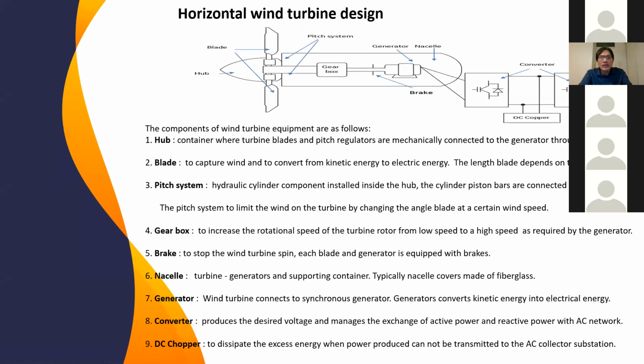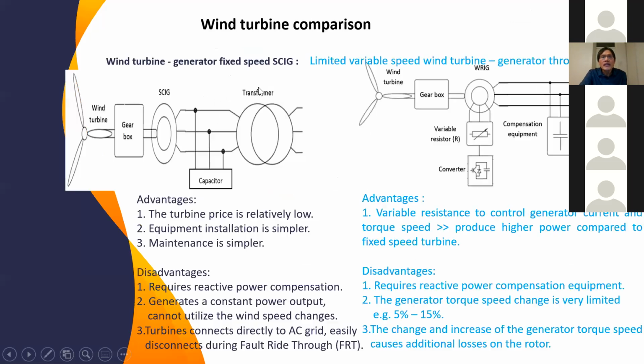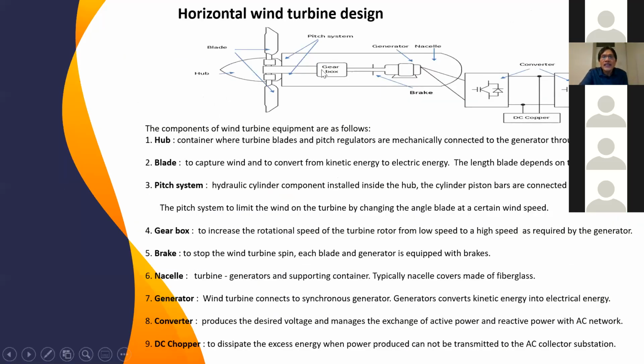The typical conventional turbine, the main components of the turbine: generator, converter, and DC chopper. The purpose of the DC chopper here is in case the energy produced by a wind farm or turbine cannot be transmitted to the AC network, let's say in onshore, maybe because of a fault, all the energy should be absorbed or dissipated. For this, we need a component, typically called a DC chopper.